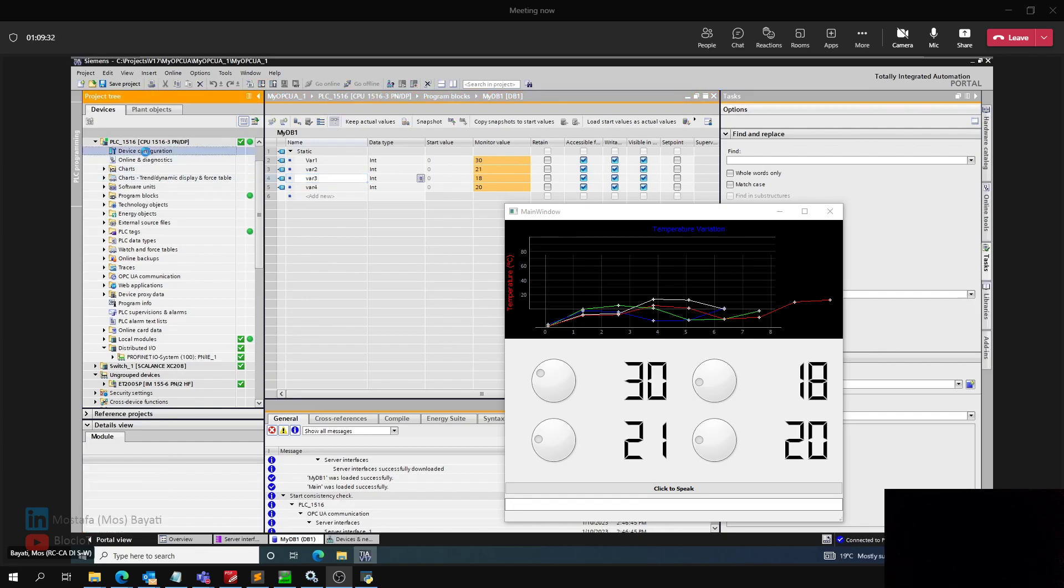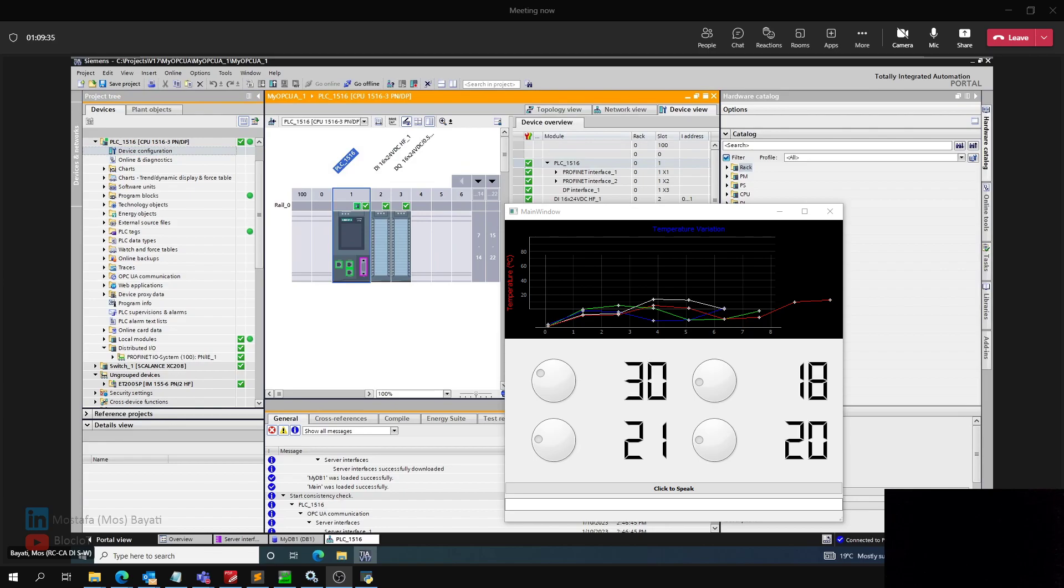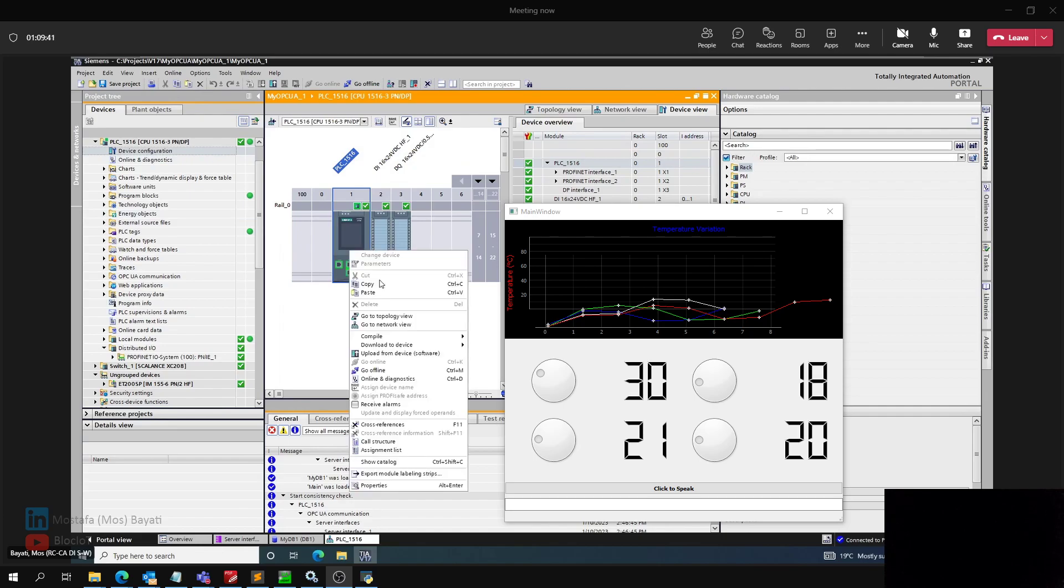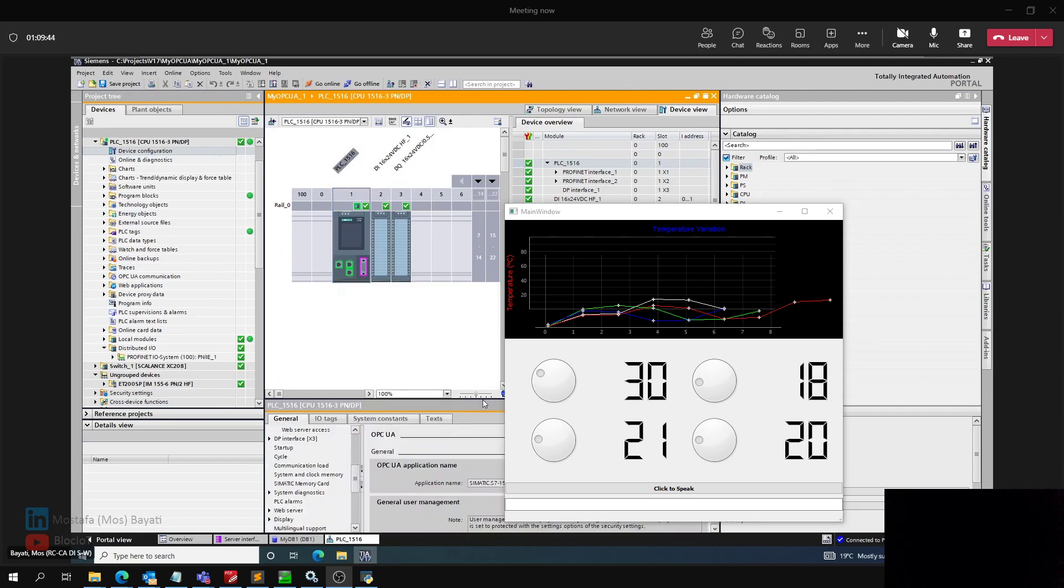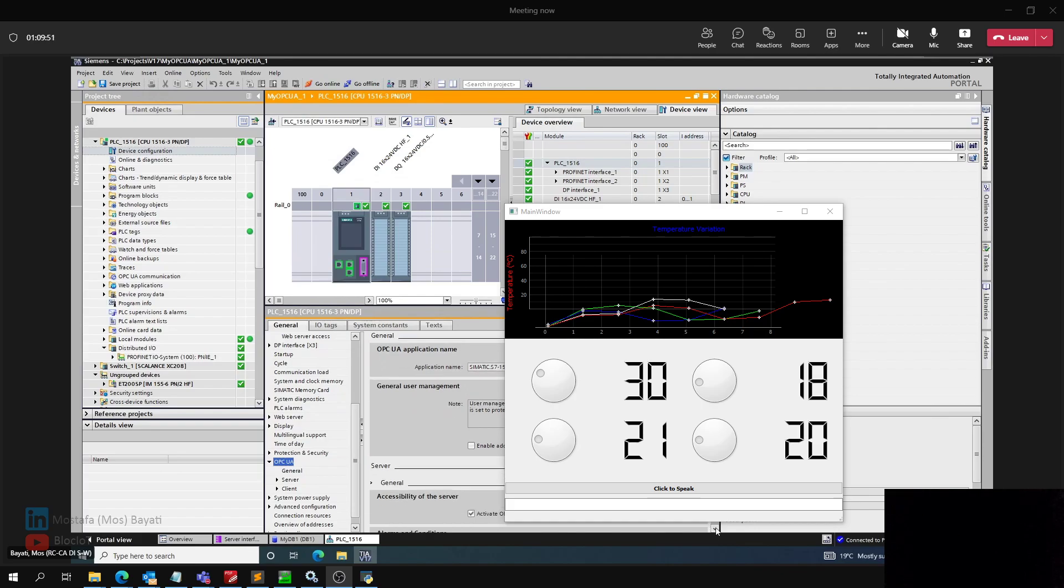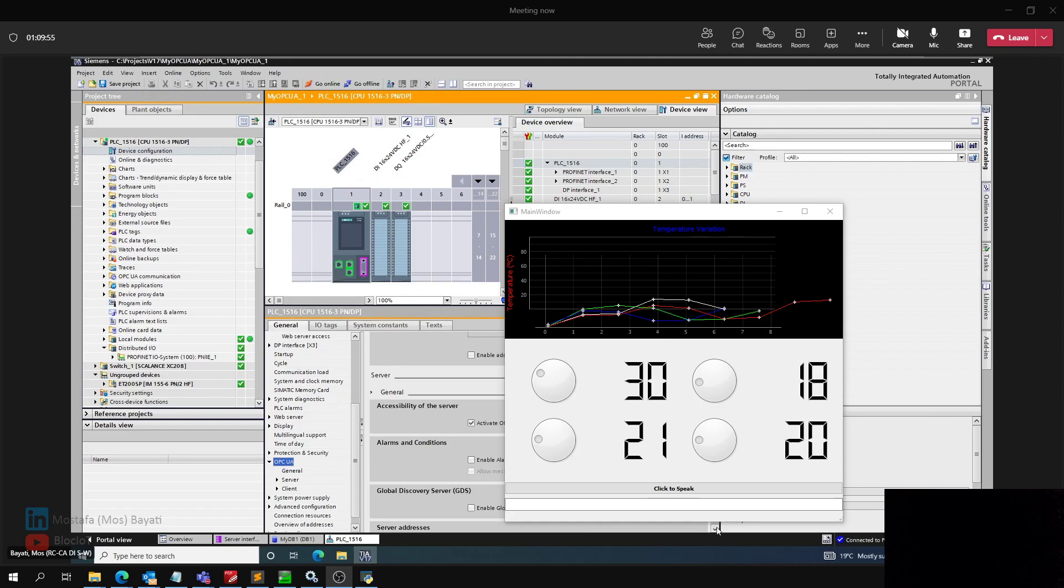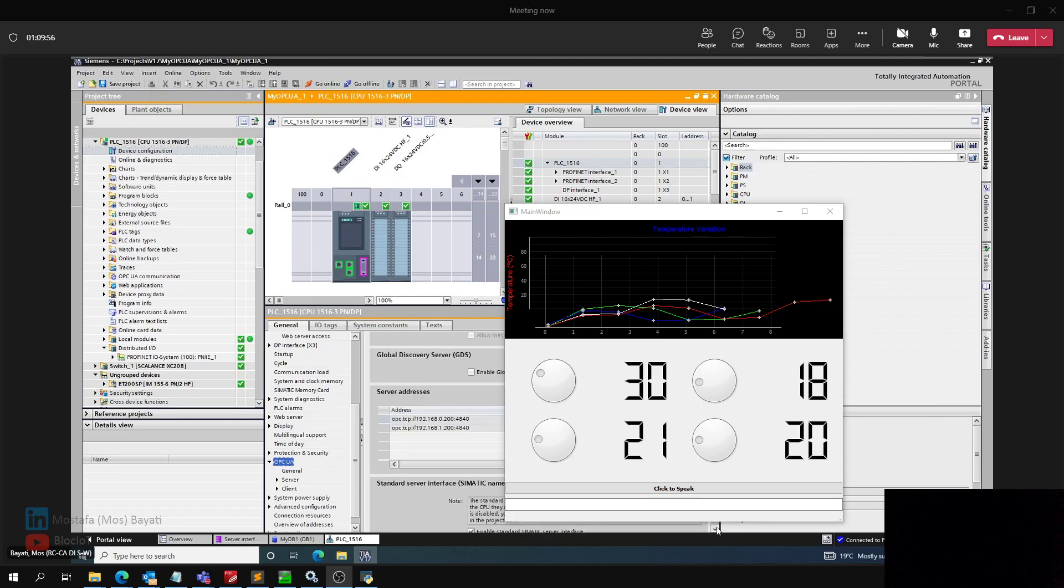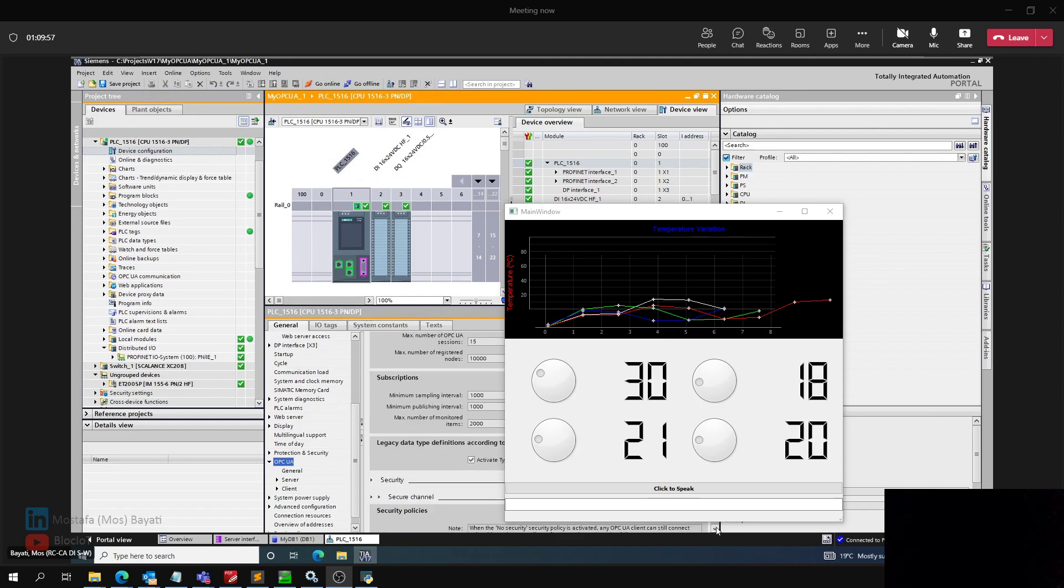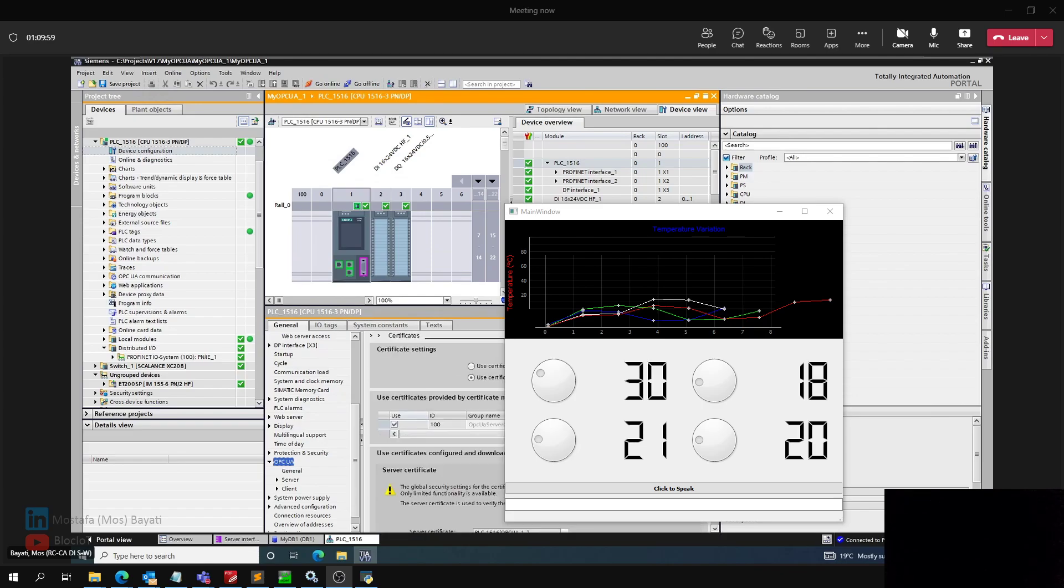If you are not familiar with how to configure the OPC UA, maybe I can quickly show you here. You just go to your device configuration or hardware configuration and go to the properties of the CPU. Then there is an OPC UA section. Just simply activate the OPC UA server.